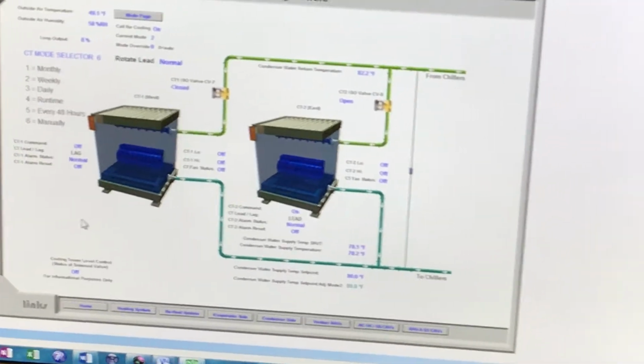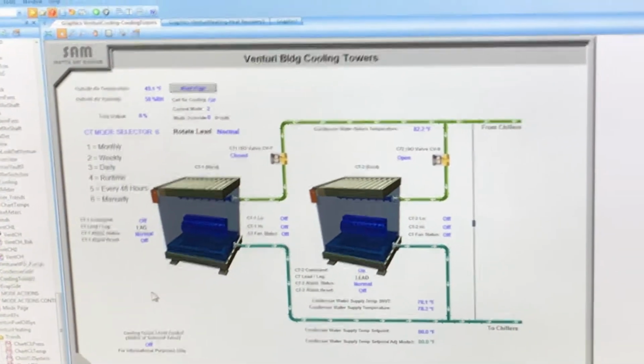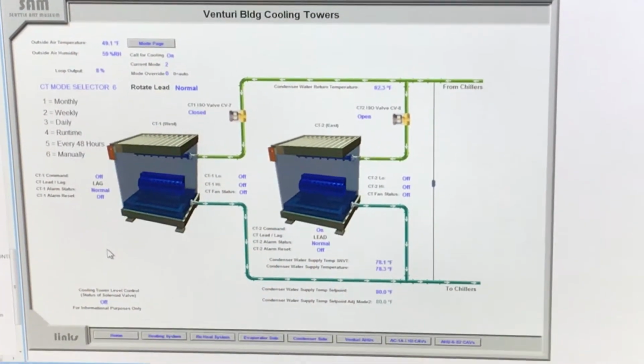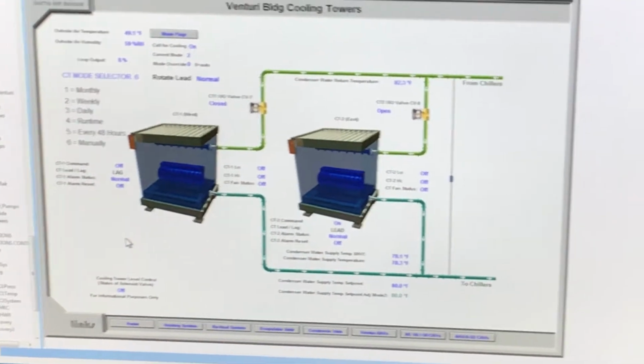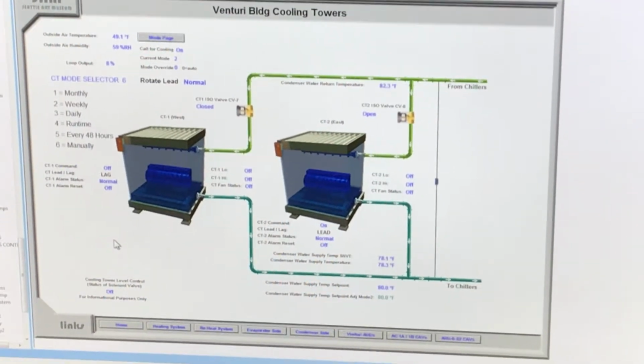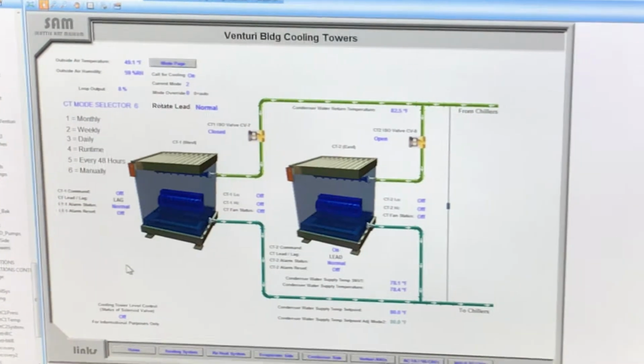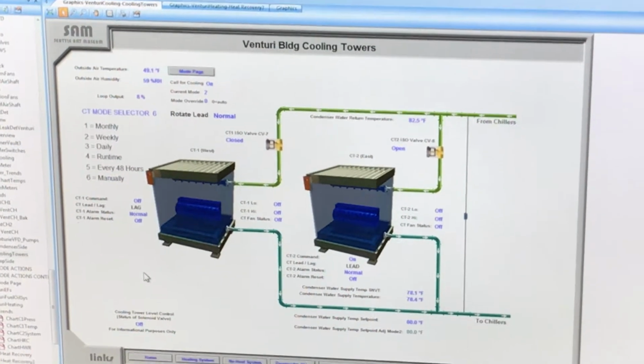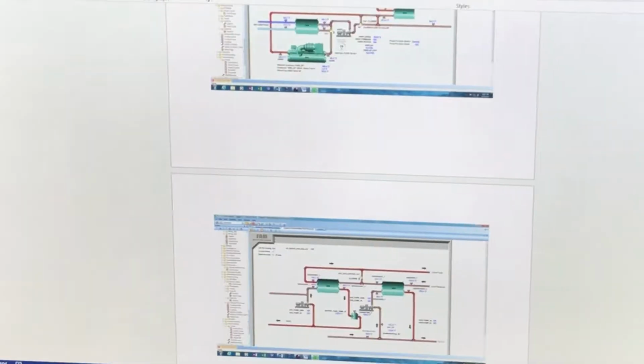But right now the reason we have it manual is because we need to fix the float on that cooling tower. So we want cooling tower 2 to be lead most of the time. Otherwise, it's going to start dumping over the overflow. Okay. Did I do a screenshot of that?